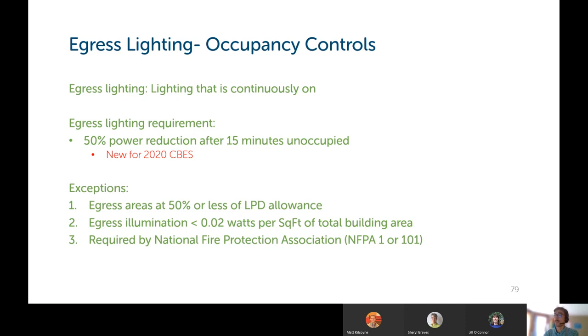Egress lighting, there is a new portion of the code for occupancy controls on that. Egress lighting is lighting that is continuously on in the building. So the requirement in this code is that there must be a 50% power reduction after 15 minutes of unoccupied time. And that was not in the old version of the code.